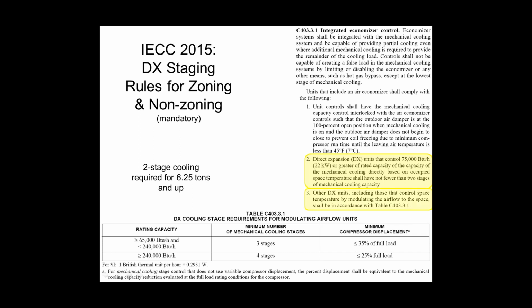The other one, which is significantly more interesting to me, is note number 3, which is on DX units, once again, whether it's controlled by space temperature or other means. If you modulate the airflow to the space, you need more stages. So what does that mean, modulate the airflow to the space? To me, that means if you got a zoning system, right? If you have a VAV, dampered zoning system, or VVT or other constant volume zoning system, a Honeywell 3-zone panel or whatever it is, if you have systems that throttle the airflow back in order to control the comfort in the space, in those scenarios, you have to have more stages of heating and cooling.